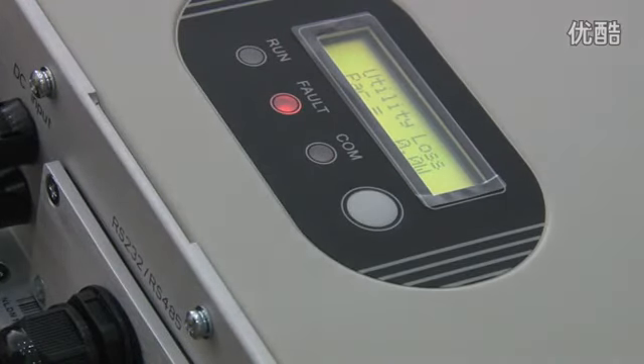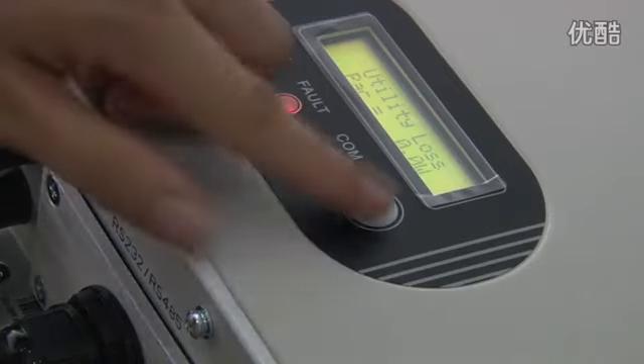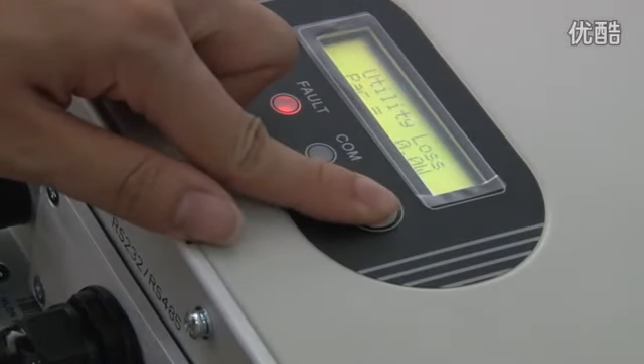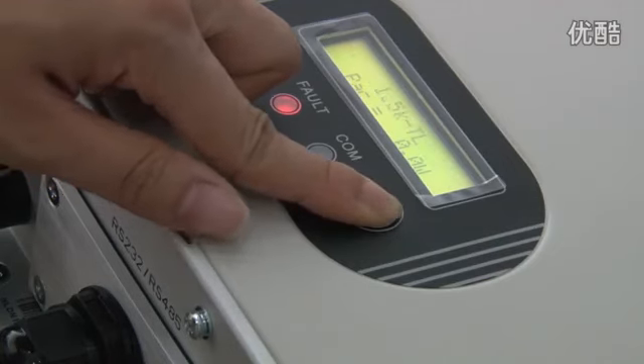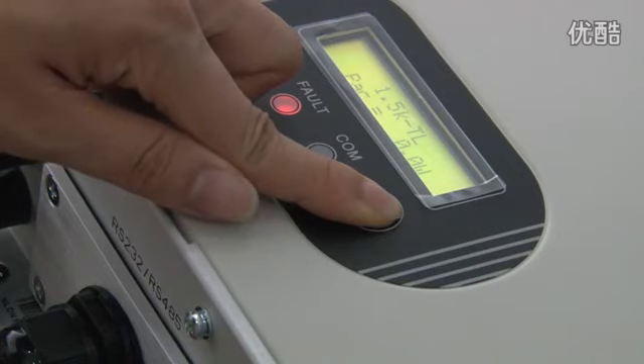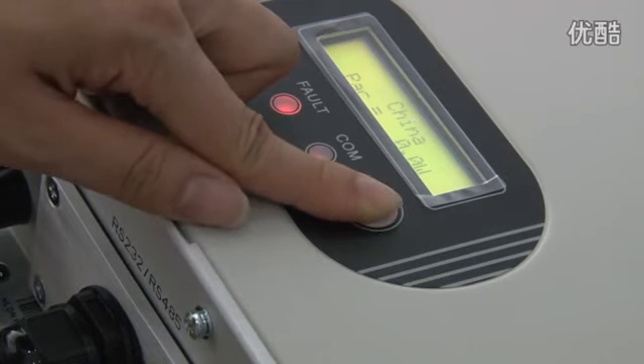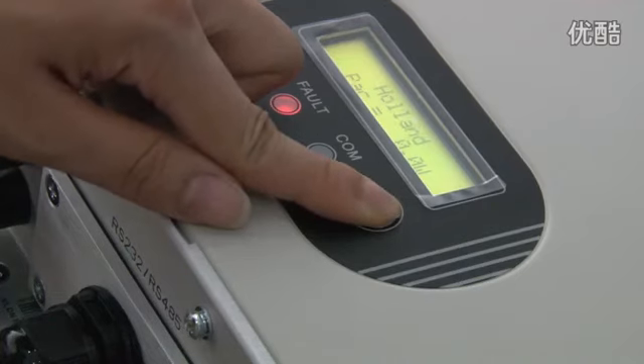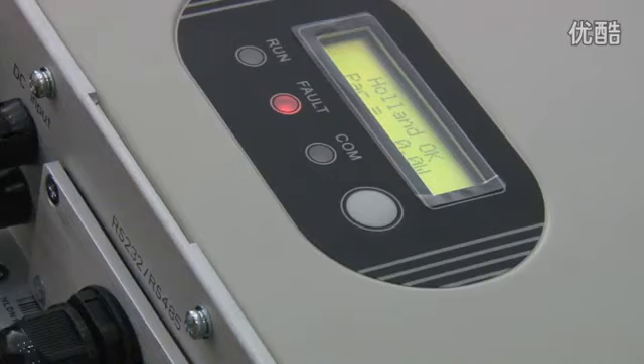When your inverter's total generation is below 1 kWh, you can change your country setting through the screen and the button. Keep pressing it until you see the inverter type, and long press the button until you see the country. Keep pressing it until you see the country you want to set to. Long press the button until you see OK. Now the country setting's done.